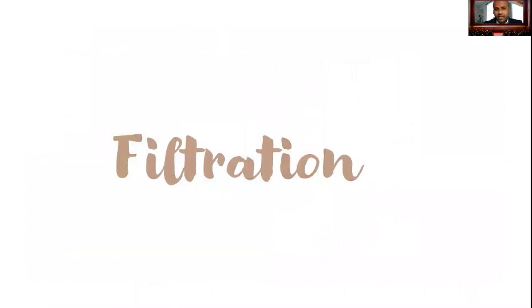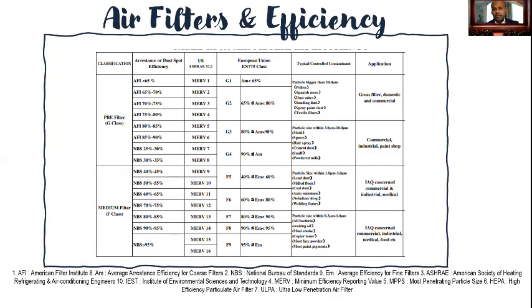The HVAC systems of large buildings typically filter air before it is distributed throughout the building. So consider upgrading HVAC filters, as enhanced filtration is a critical solution to maintaining healthy indoor air quality. ASHRAE's current recommendation is to use a filter with a MERV of 13. Of course, MERV 14 or better is preferred. A MERV 13 filter is 85 to 90% efficient at capturing particles in the 1 micron to 3 micron size range. On the screen now, you're looking at filter efficiency for different filters. Generally, the higher the MERV, the better the performance.